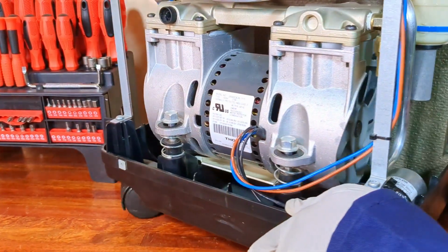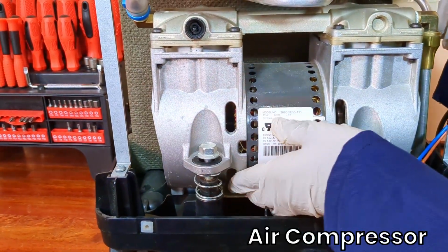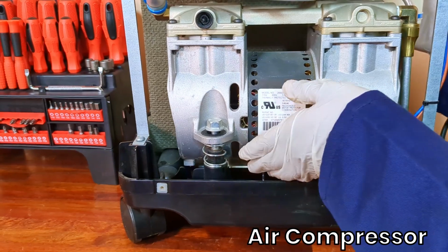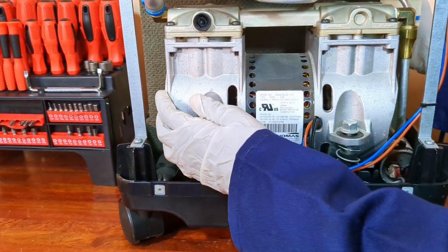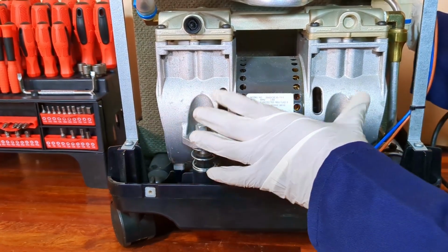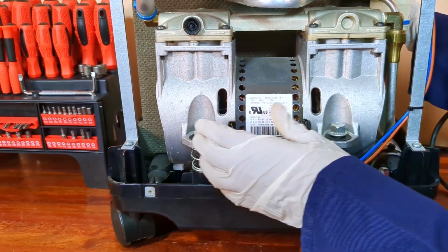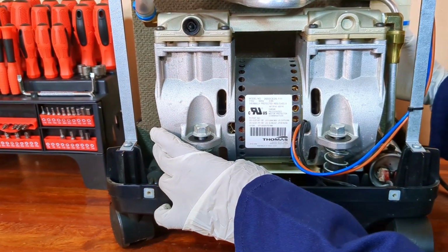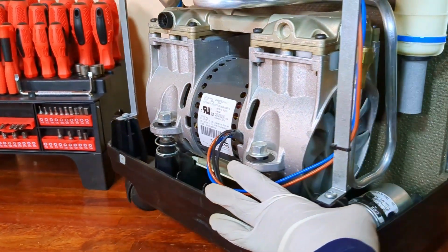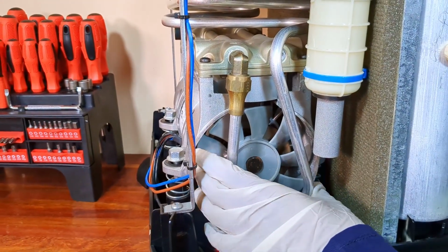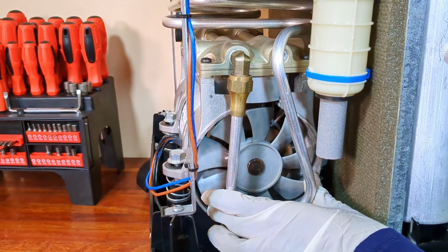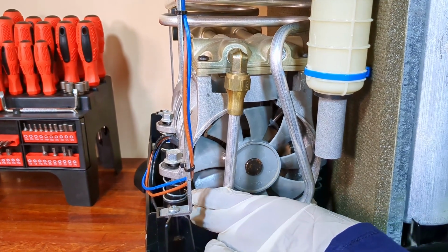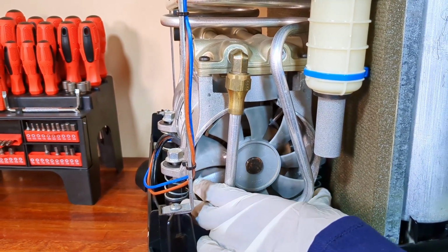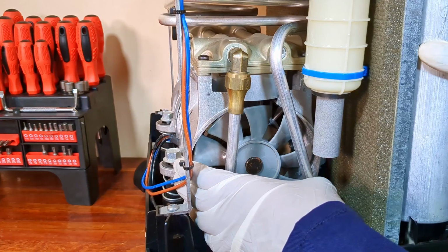Now moving to the front, we have the concentrator's compressor. This compressor is of the Thomas brand 2660 series. It draws in ambient air and compresses it to a pressure of 21 psi before this air is delivered to the sieve beds. This compressor has two fans, one on this side and another one on the other end. And these fans are used to draw in ambient air and provide cooling to the compressor.